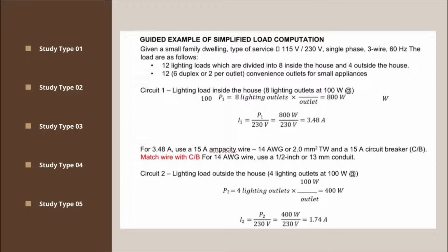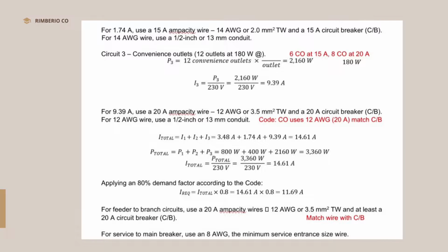So for circuit 2, lighting loads outside the house, 4 lighting outlets at 100 watts. So electric power P sub 2 is equal to 4 lighting outlets times 100 watts over 1 outlet, which is equal to 400 watts. So next is electric current I sub 2 is equal to P sub 2 over 230 volts, which is equal to 1.74 amperes. So for 1.74 amperes, use a 15A ampacity wire, 14 AWG or 2 mm squared TW, and a 15A circuit breaker. So for 14 AWG wire, use a 1/2 inch or 13 mm conduit.